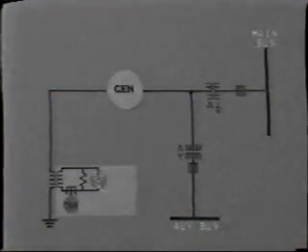Quite often in this ground protection arrangement, a CT is installed in the secondary circuit, and this operates an instantaneous overcurrent relay to provide backup for the overvoltage relay. In many generators, some third harmonic current flows through the neutral under normal operating conditions. This is because the generated sine wave is not perfect, perhaps due to the design of the generator itself, or more likely, the loads which are being imposed upon the generator. The ground fault relays must be isolated from these third harmonic components in order to prevent inadvertent tripping. This is usually achieved by a tuned circuit in the relay itself, which blocks these components.